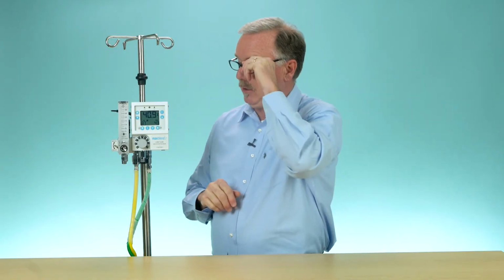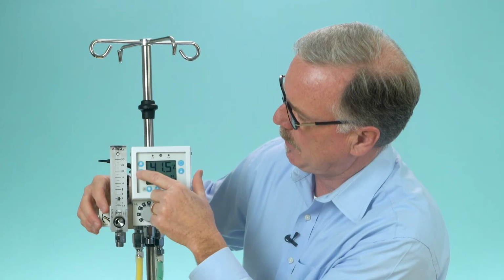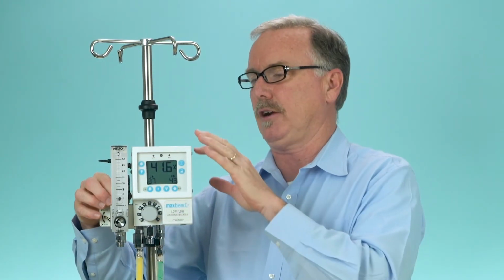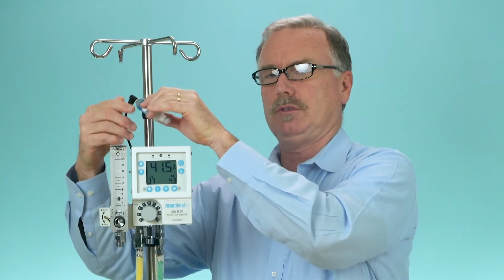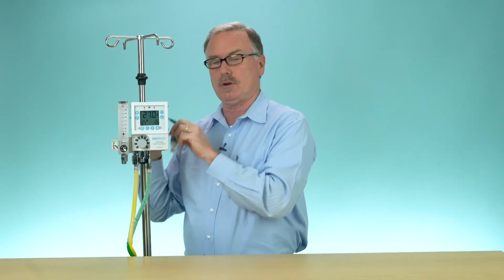So another thing that you may take in consideration is, let's say I have a room air gas source. I have a room air flow meter. Or I have a 100% gas source with an oxygen flow meter on the wall. You could remove this. Once again, I would suggest hitting alarm silence. Patient still getting therapy. I could remove our fuel cell. I could put it into the known gas source of room air or 100%.